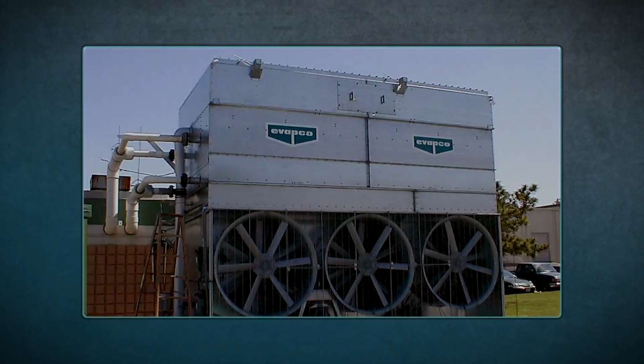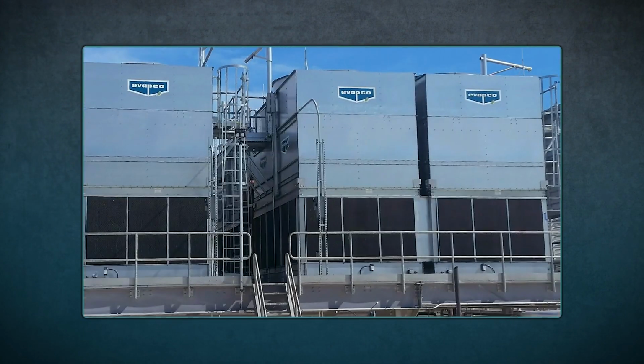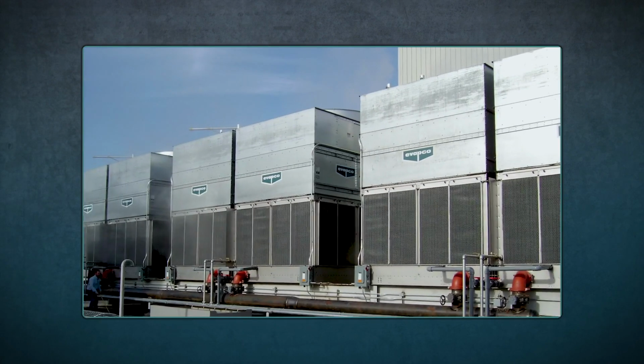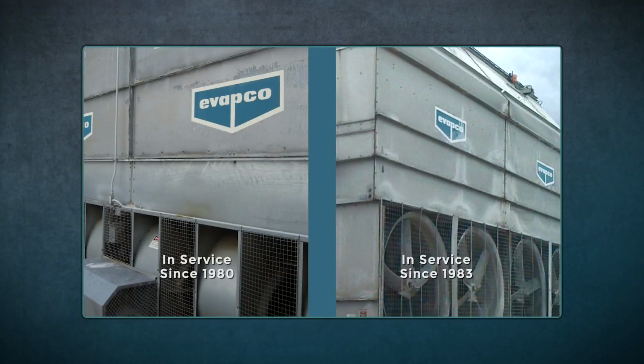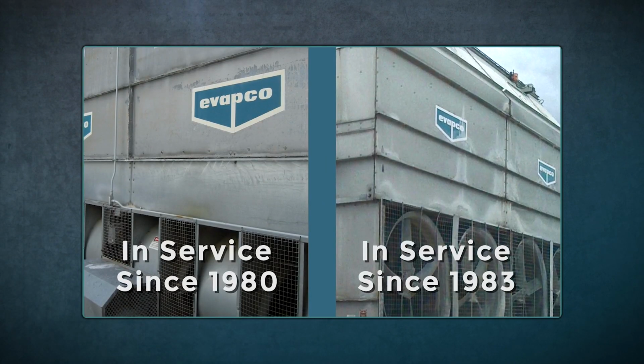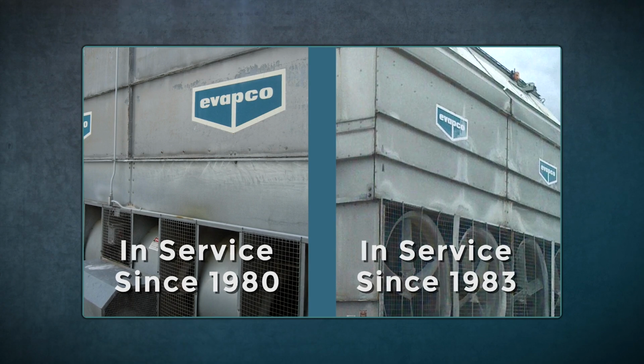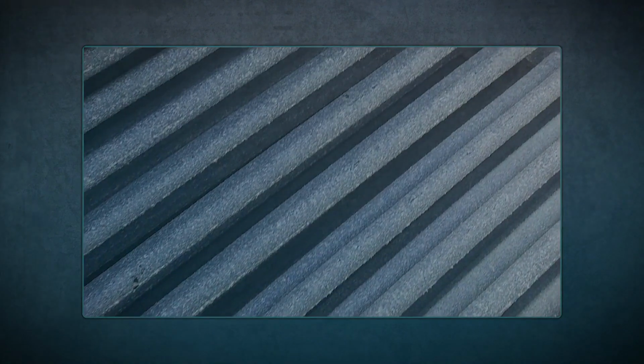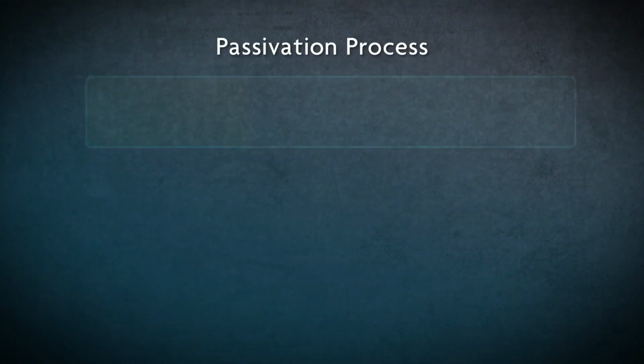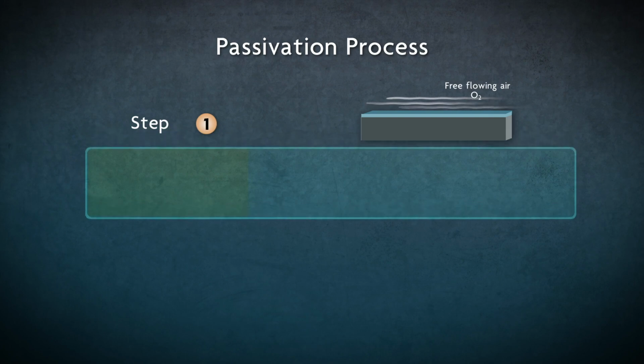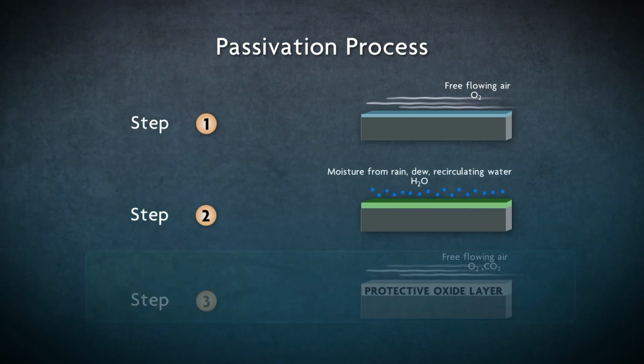Galvanized steel has been the preferred material of construction for evaporative cooling equipment for over 50 years and provides a long service life when properly treated and maintained. However, a form of premature zinc corrosion known as white rust can occur on new galvanized surfaces. To help minimize white rust, galvanized surfaces need to develop a protective oxide layer through a process called passivation.